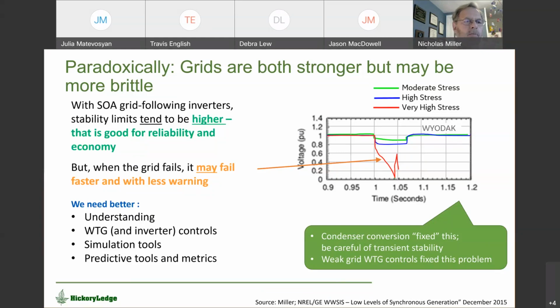The green and blue traces didn't show a substantial post-fault voltage dip that we're used to looking for. The system went from pretty sleepy, stable cases to a fail during the fault, which is one of the things Julia showed. So that's the bad news.